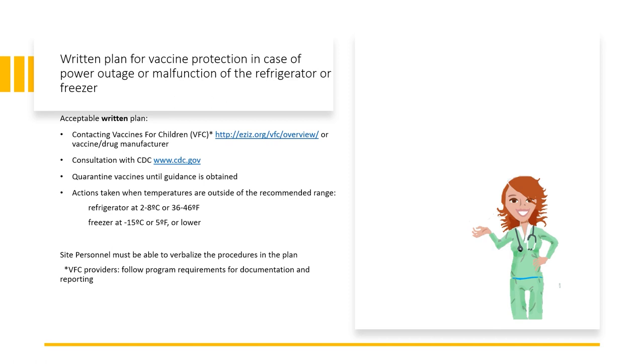It is important to quarantine the vaccines until guidance is obtained. Action must be taken when temperatures are identified outside the recommended range. Please note that the refrigerator must be maintained between 2 and 8 degrees Celsius, or 36 to 46 degrees Fahrenheit, while the freezer is minus 15 degrees Celsius or 5 degrees Fahrenheit or lower.